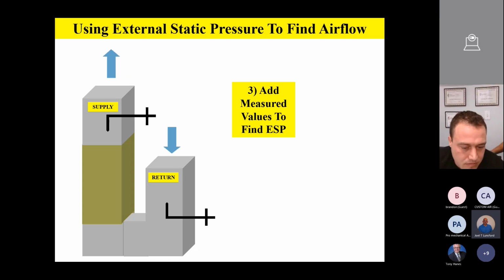That's perfectly fine, because you got to remember, an air handler includes the coil as part of the static pressure reading on the chart. On a furnace, the coil's not included on that chart. So you have to go underneath the coil on a furnace. But on an air handler, it's included. So if you'll go on the return side here, like I said, it depends on your manufacturer. If you've got a negative pressure air handler, you'll have the fan, then you'll have the coil. But most manufacturers, us included, the coil is part of that static pressure chart.